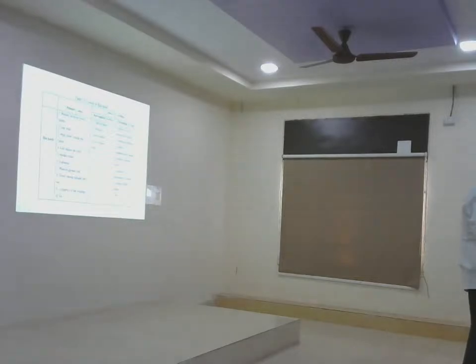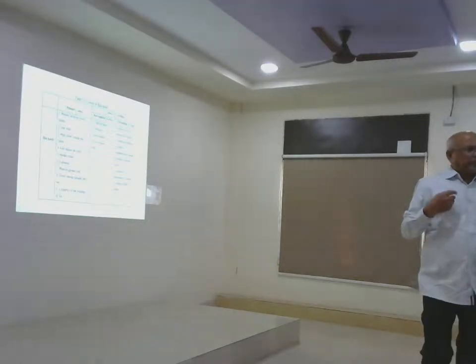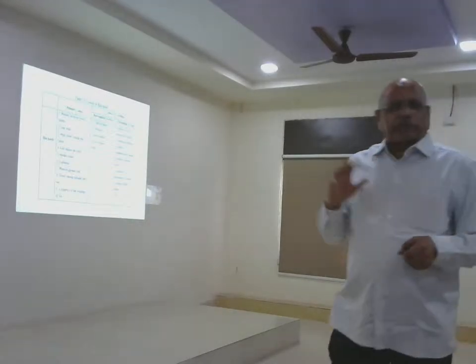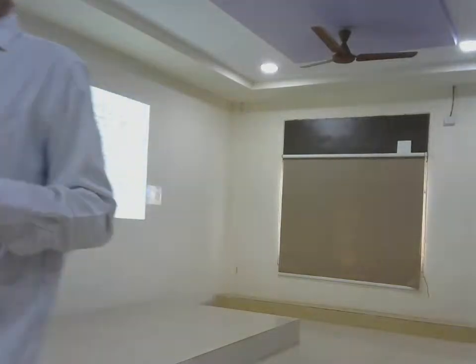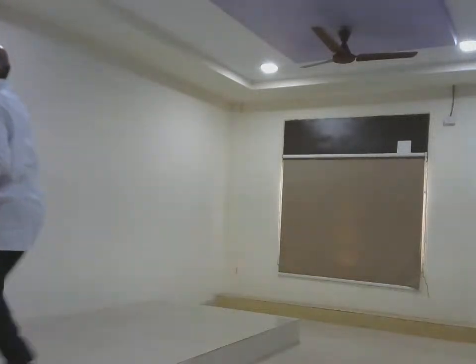The frequency depends on real power. I always talk about real power and reactive power—if you understand real power, reactive power, and loads, you can study the rest yourself. Real power balance occurs when total generation equals demand plus losses. If both are matched equally, I can maintain the frequency exactly.